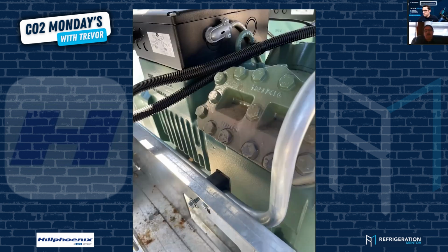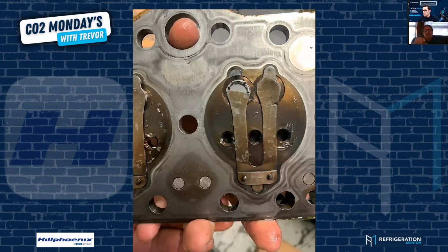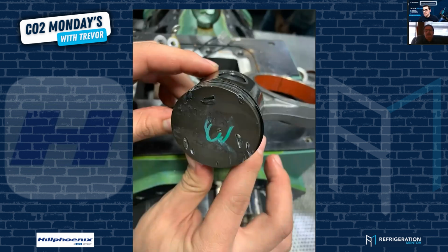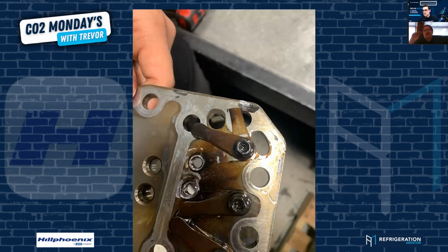We broke the compressor down. We pulled the heads apart. Do you have the pictures with the heads? These were the heads. This is after the first visit to pull the compressor apart. This is after it disintegrated. But before that, they had just baked the oil on the discharge valves. They were glazed a purplish color from the temperature. You see how the oil is baked on it. This rack has only been running 5 months.